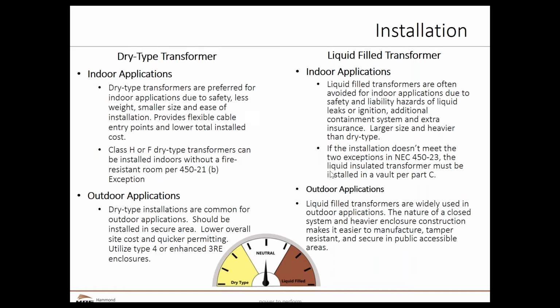Generally, the transformer won't be as heavy and won't require as much of a concrete pad. However, a dry type transformer is cooled by air, and inherently there is going to be an air transfer. So if the area has a lot of dust, especially if it's conductive dust, like a coal plant or something like that, that could be a big concern. We can build transformers that are what we would call non-ventilated, but those tend to be significantly larger and more costly than a ventilated unit.